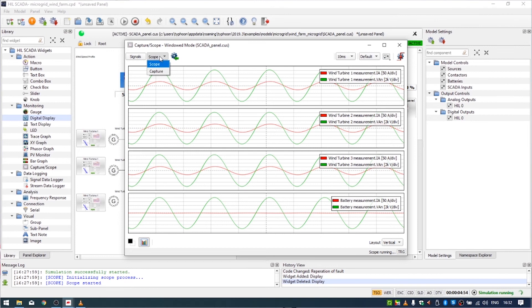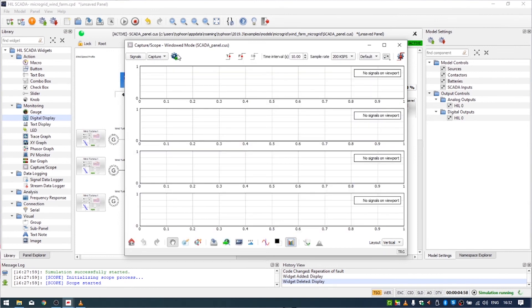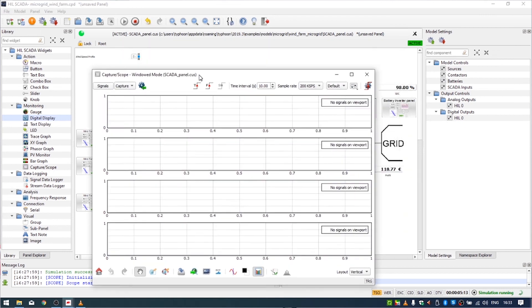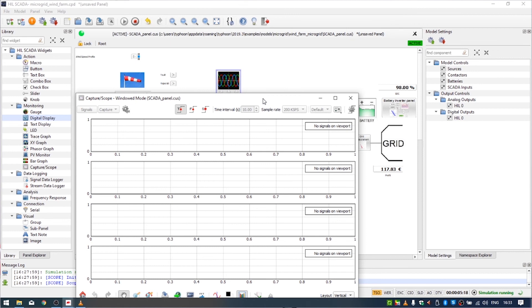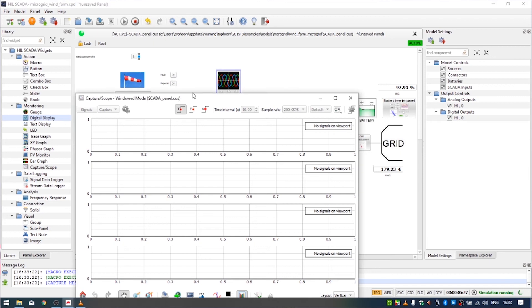To observe the fault the best way is to go to capture and import settings from scope. We can set a trigger on the PCC contactor. Let's trigger and then introduce a fault in the grid. Here we can see the transitions during the fault. In this case we use the battery inverter as the grid-forming component in our microgrid.